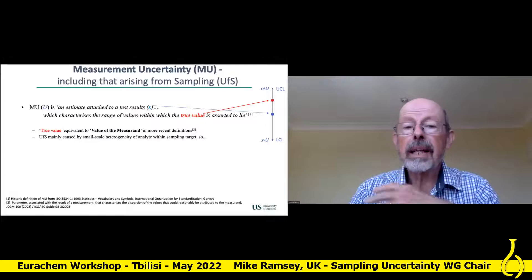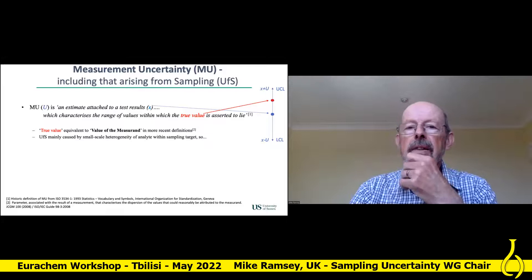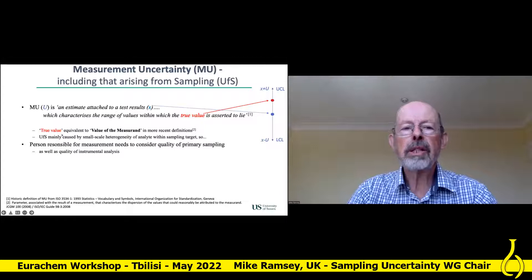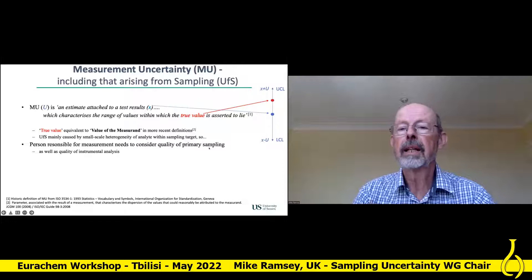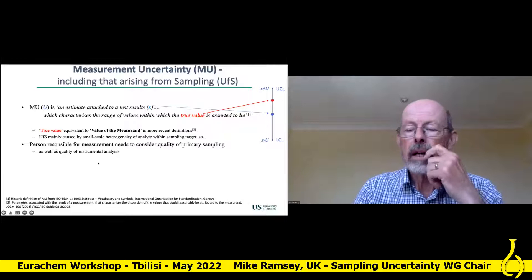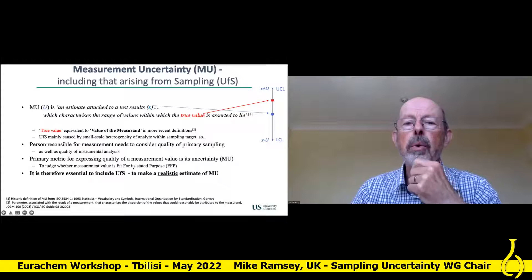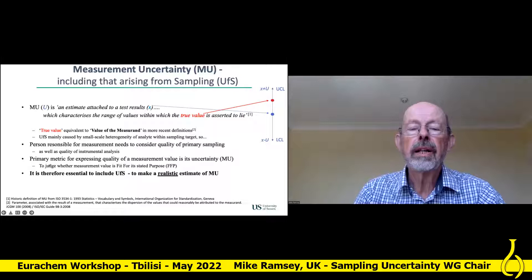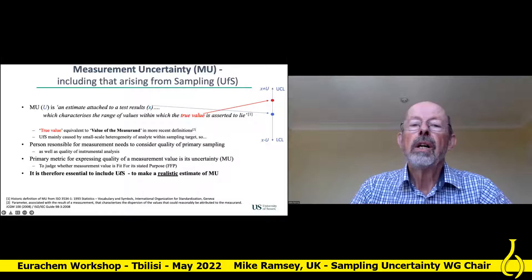The uncertainty from sampling is mainly caused by the small-scale heterogeneity of the analyte within the sampling target — so it's inescapable. The take-home message is that the person responsible for the measurement needs to consider the quality of the primary sampling. We can no longer separate the two out and say that's nothing to do with me. It has to be someone's responsibility. It's not just the chemical analysis.